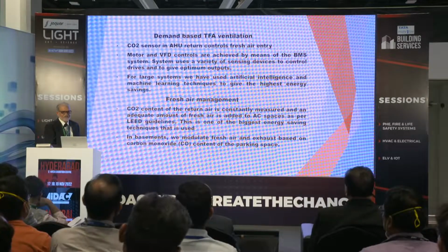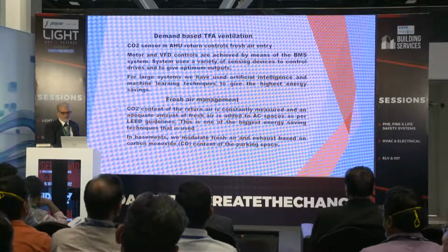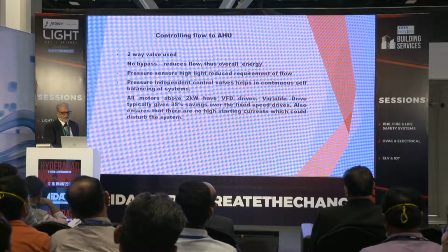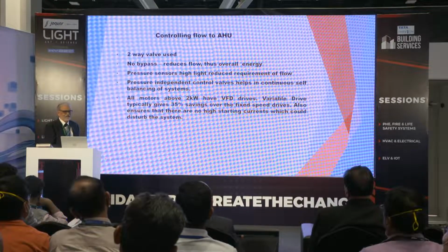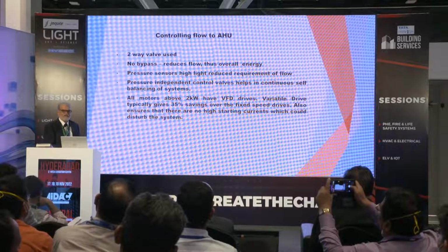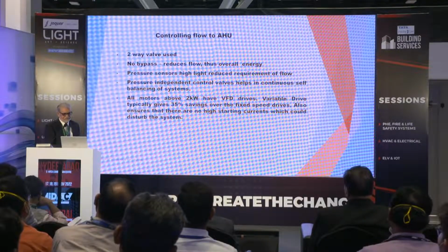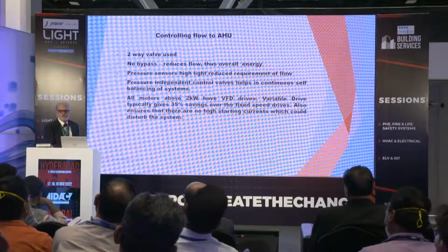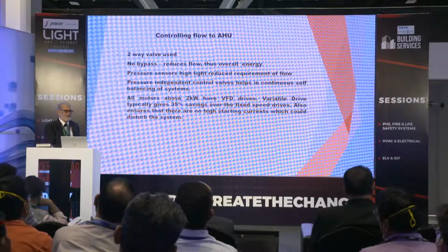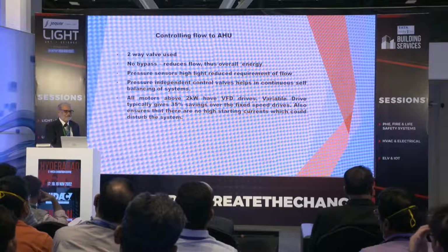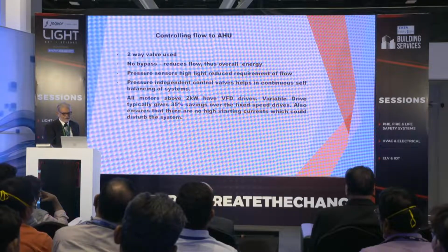In the basements, we have CO content monitors, which help you on this. We have two-way valves. We have not taken the standard valves. We have pressure independent control valves, which help in balancing the system. All motors above 2 kilowatts have VFD drives, which save about 35% of our power.